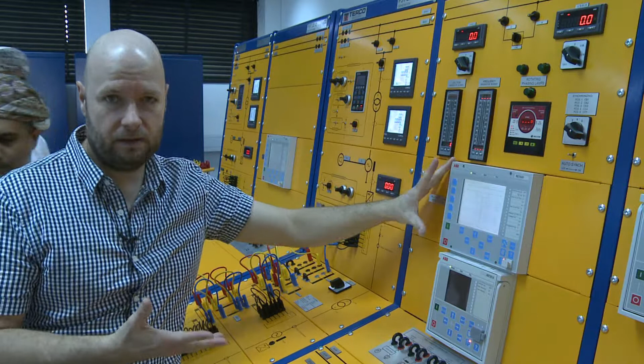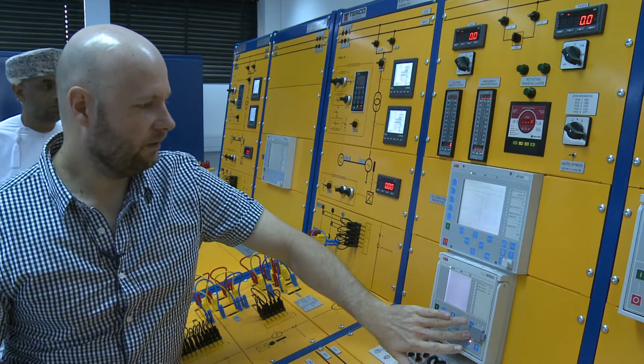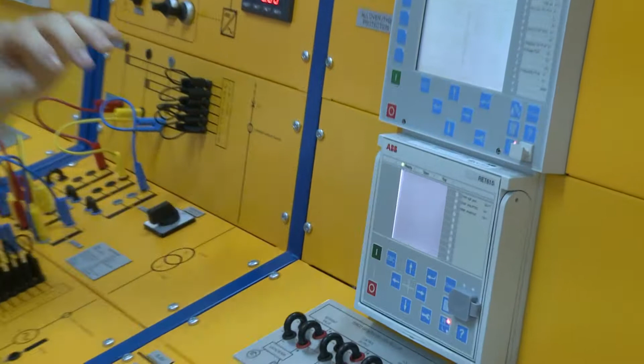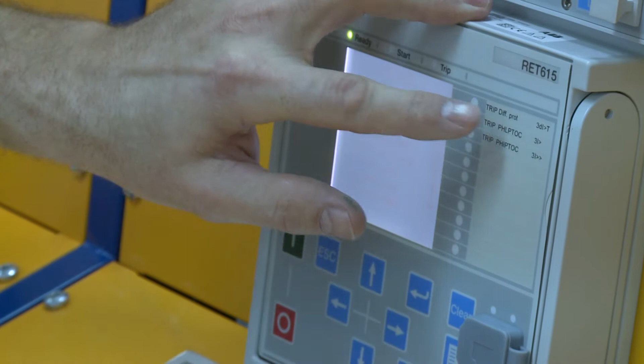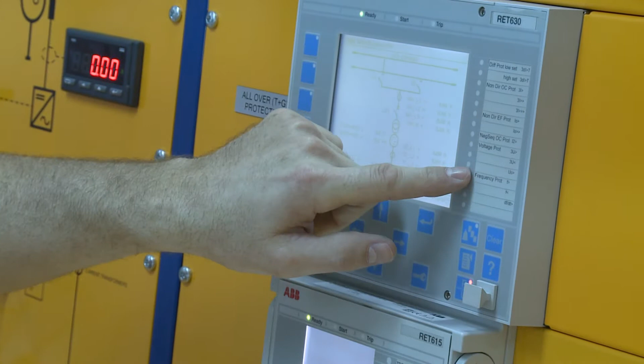We have this IED here. This is our main protection overall, and it's covering the transformer and the generator. We see here this one is our generator protection only. So these two here on either side of the generator have similar functions. They both have differential protection. They both have overcurrent of different levels. This one has a few more: earth fault, negative sequence overcurrent, undervoltage, overvoltage, and residual overvoltage. Also, we have frequency protection in this one as well. So we will go through and make all of these faults.